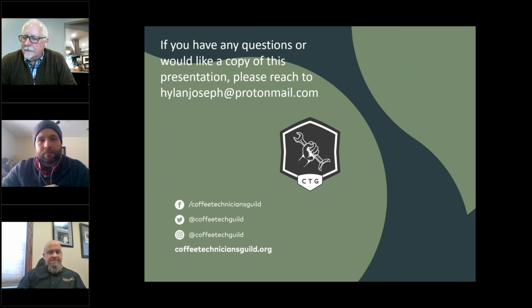If the customer requires it, you're going to end up spending a lot more time in the location, going back and forth to the circuit panel. If you can't convince them that unplugging a machine actually has a benefit, there's not much you can do. I'm adamant about it because I try to be as persuasive as I can. Hardwiring a piece of equipment like that is just too risky to me. It's carrying a lot of load. It's usually out front where people can actually use it and see it. You can't protect it from customers generally. You can't protect it from users. The ability to unplug a machine is important. I know that in a convention situation, they're wiring things together with wire nuts and taping the hell out of it all the time.